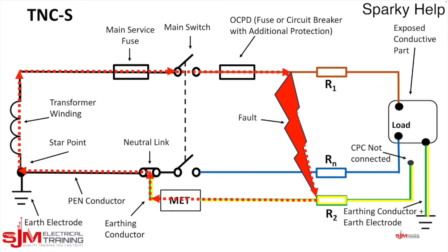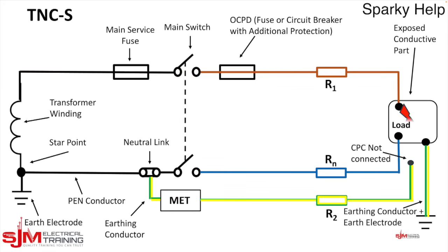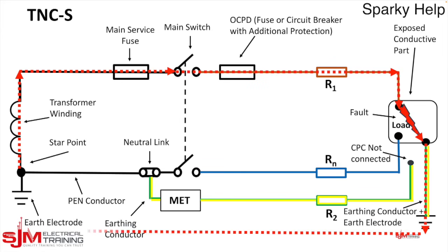But what happens if you have a fault in the outside now, aligned to your newly created earth, your TT part? Well, current will flow, providing you've got enough resistance there, or not enough resistance, depending on how you want to view that. So we develop a fault. Current, therefore, will flow from the original building, down your earthing conductor, through the earth electrode, and through to the earth, back to the star point of the transformer. This then solves the problem of exporting a stray voltage and or picking up anything else, because you're completely isolated from it. Because you've created your own earth path.